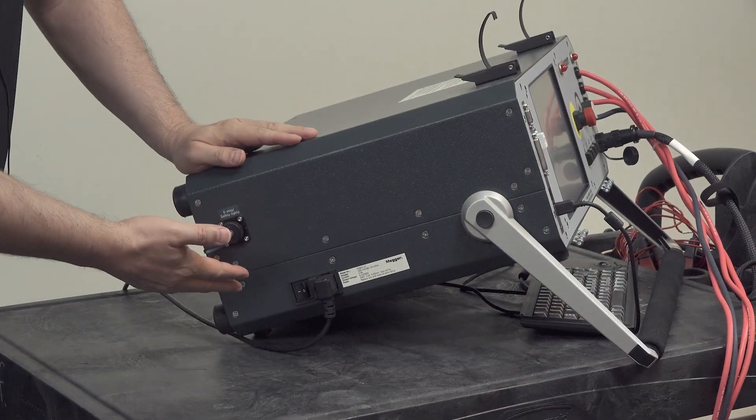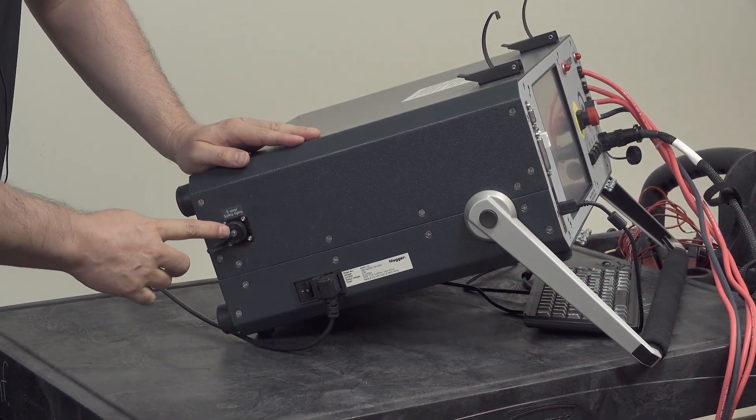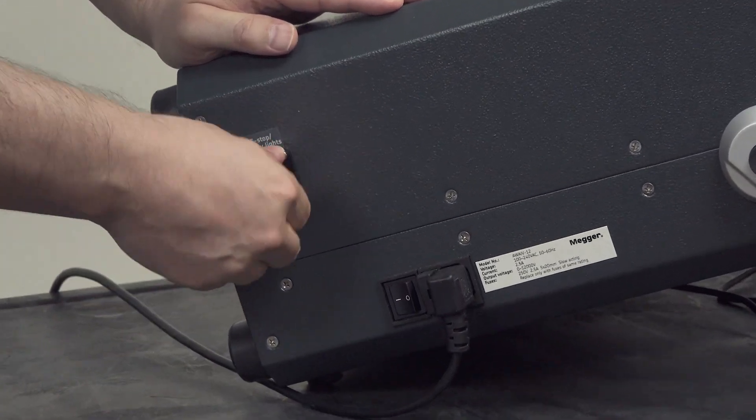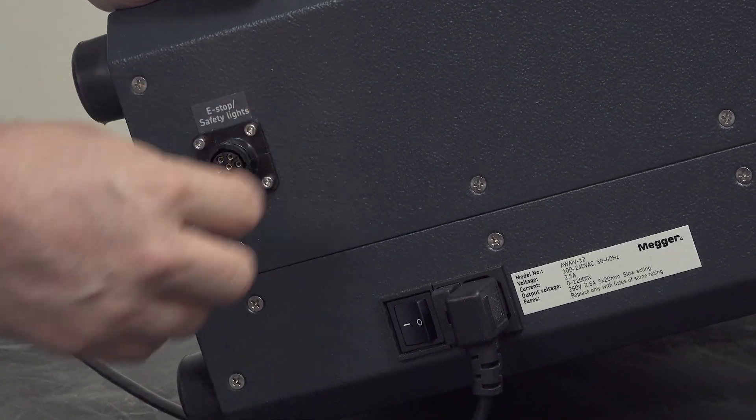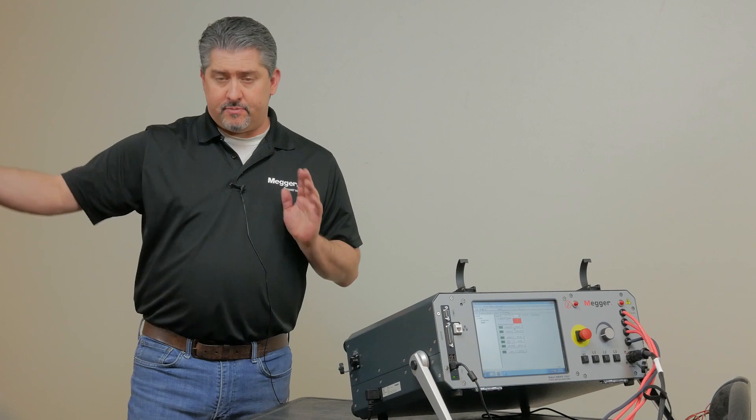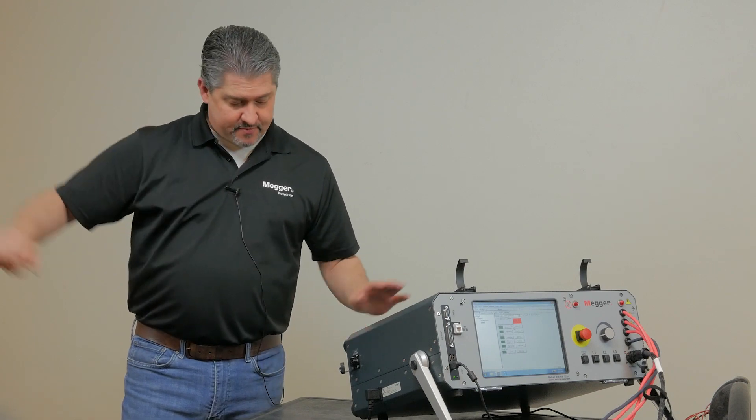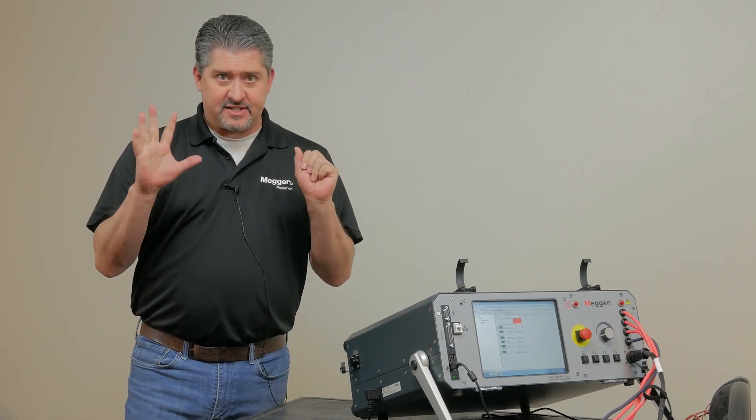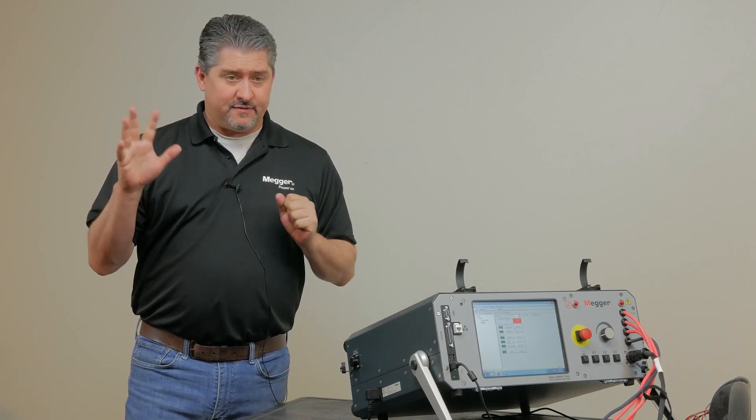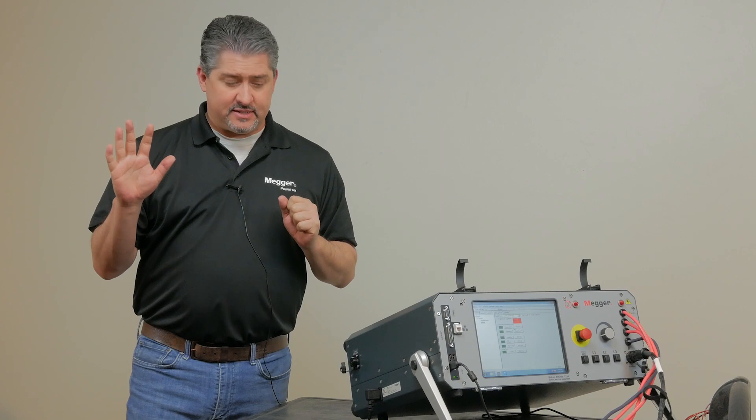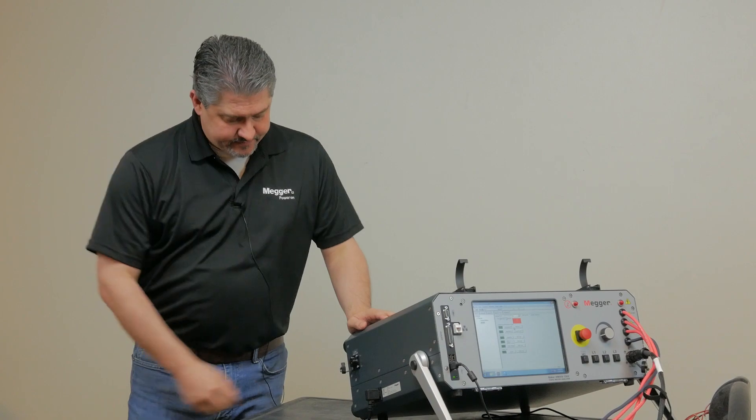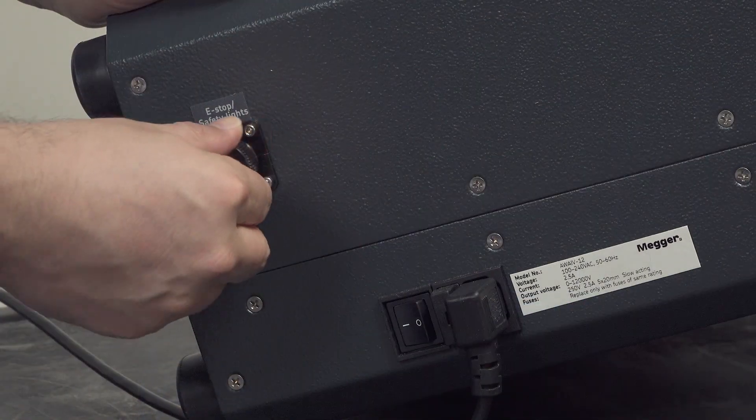On the side panel of the AWA we have a connector for a remote e-stop and safety light. Here we could connect an optional accessory that allows for an e-stop away from the tester, as well as very obvious safety lights that let everyone around know that you're performing testing. Flashing red light for high voltage leads energized and a solid green light for testing secured.